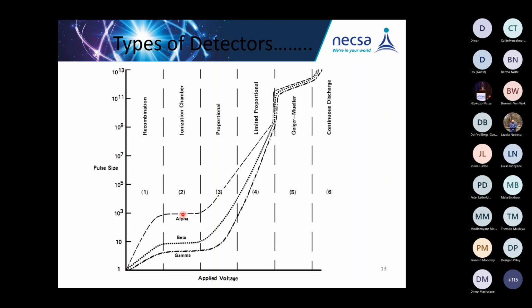Voltage. When the instrument is calibrated, especially for a surface contamination monitor, we set up the operating high voltage. And that high voltage will be defined in the setting before in the certificate and the setting after. There's a table which shows you all the settings. Please, please, I'm begging and I'm pleading with everyone: when you see a setting before and setting after, make sure that when you take your instrument for QC and also to the field, your settings correspond with the setting after calibration.